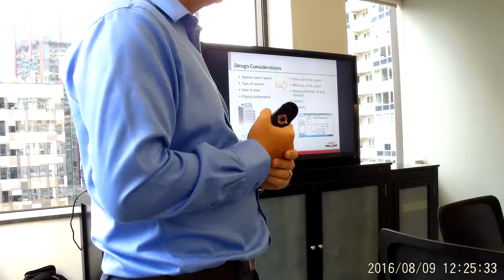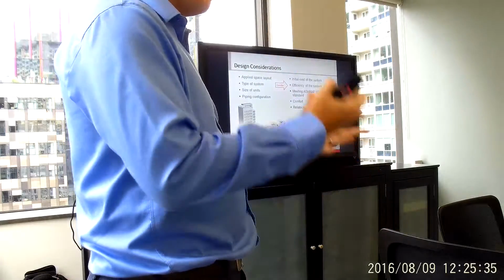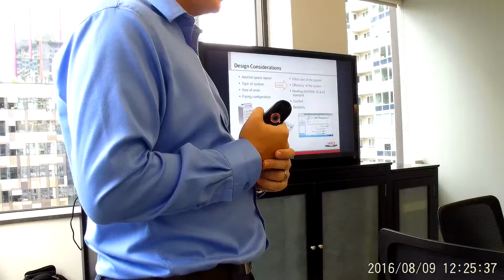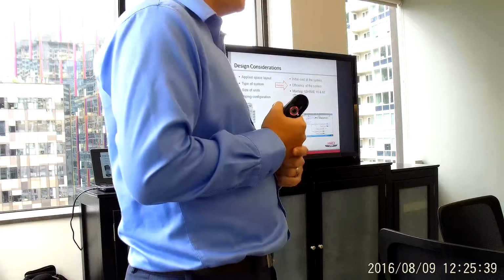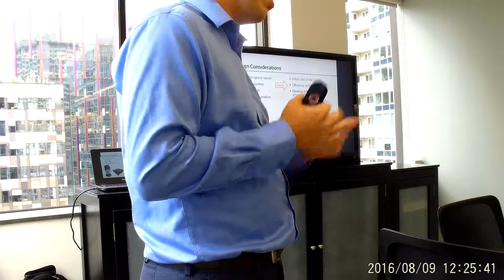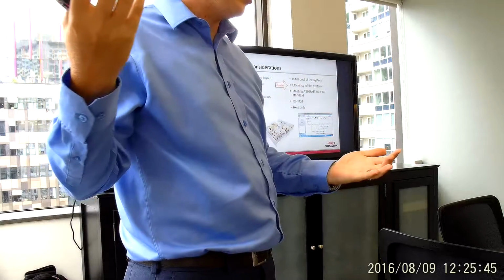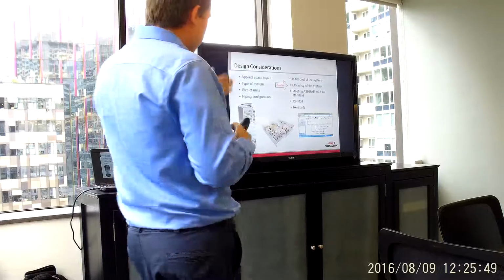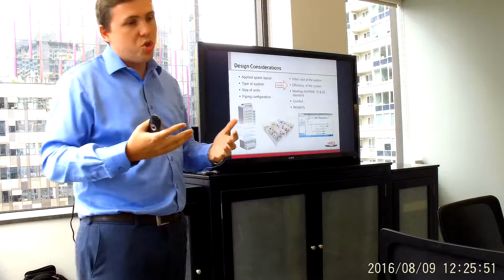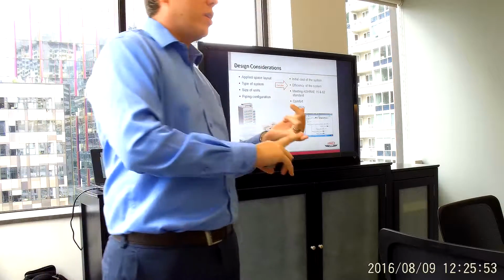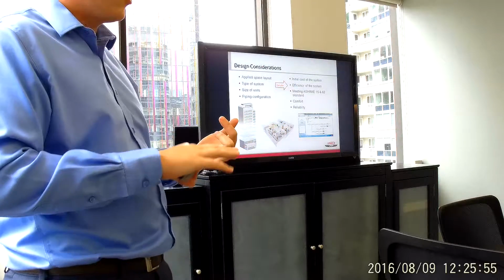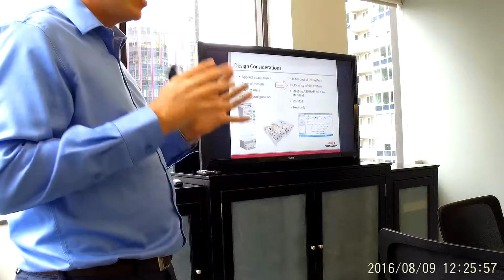So how is that any different from having a catastrophic leak in that space, with air running out into your corridor pressurization system? There's continuous air movement into that space and therefore out of it. That being said, under a catastrophic failure, ASHRAE 15 requires that we make sure we're within limits, and that is elevation-based - to a lesser extent region-based, but mainly elevation-based.